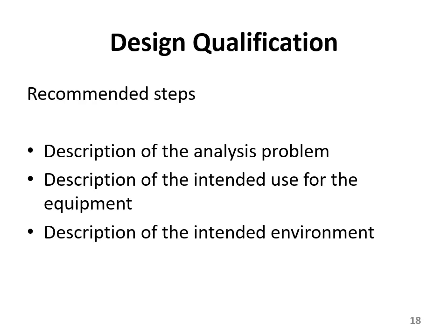There are a few steps which, if you follow them while doing the design qualification, help you a lot. What is helpful is to describe the analysis problem. If you are getting some problem, describe it. Describe the intended use of the equipment. If you are using an equipment, what is the intended use? Design it properly. Describe the intended environment, the environment where you are going to use the machine. That is also important. Describe it.